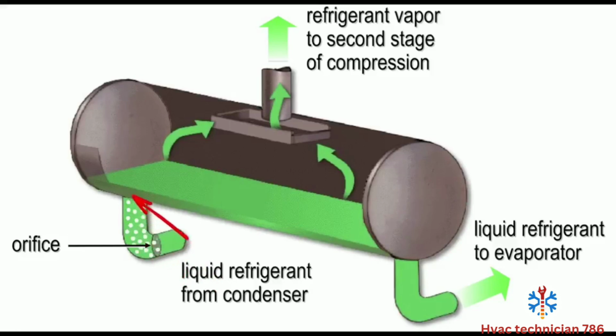And that refrigerant flows through here into our economizer. This is an economizer you would see on a CVHF. So our point here is the refrigerant's going to flow in. It's going to pre-flash here, and this is going to be a medium pressure state. Coming from our condenser, we're a high pressure liquid refrigerant. Flowing in here, we're a medium pressure saturated refrigerant.